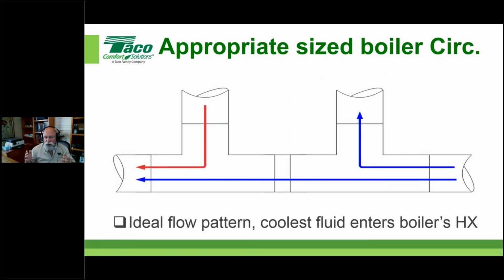I'm just blowing up those two T's, showing you the ideal flow pattern that we're looking for, because we want the coolest water temperature to go back to the boiler. And if you're looking at this, you're going to surmise that if I've got water going up here and water going this direction, and I have this blending back in here, then this GPM is going to be equal to or slightly less than this GPM. We're just splitting the flow here. But the idea is I don't have any of this heated water coming back across the top and coming in here. So that's why we say this is in a primary secondary configuration, this is the ideal flow pattern. We'll give it a thumbs up.